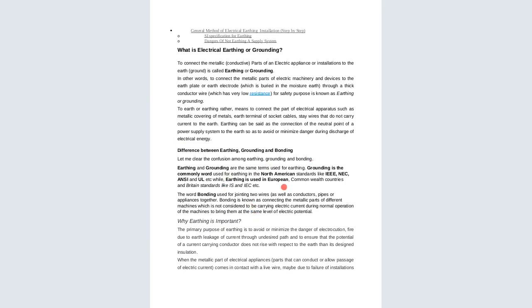What is the difference between earthing, grounding, and bonding? Let us be clear on this. Earthing and grounding are the same terms, as I had already said. Grounding is the word commonly used in standards by the IEEE, that is the Institute of Electrical and Electronics Engineers, while earthing is used in areas like the British standards, the Commonwealth countries and the IEC. The word bonding is used for joining wires, conductors, pipes and appliances together. Bonding is connecting the metallic parts of different machines, which are not considered to be carrying electric current during normal operation, to bring them to the same level of electric potential.